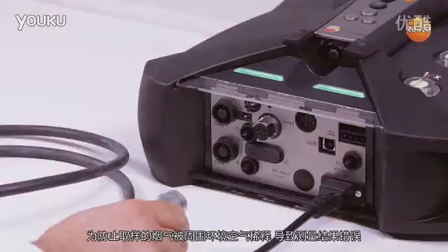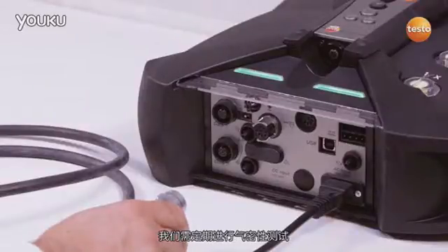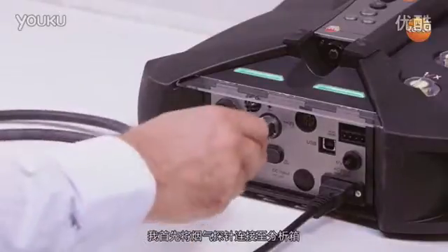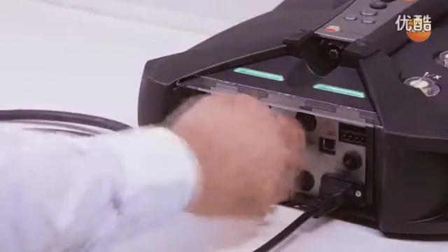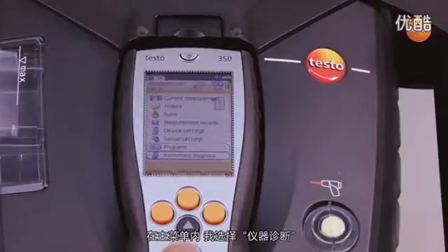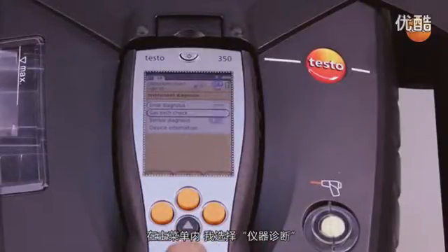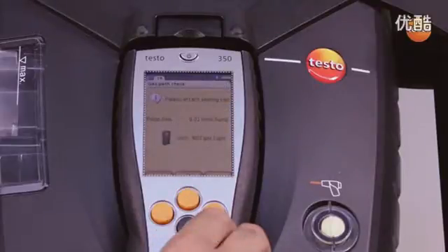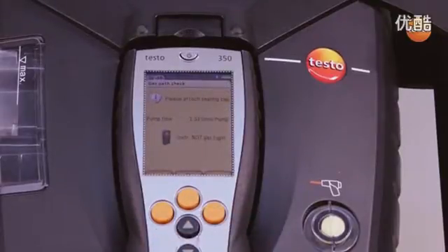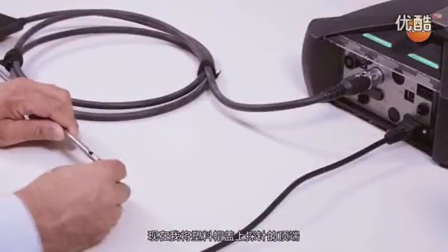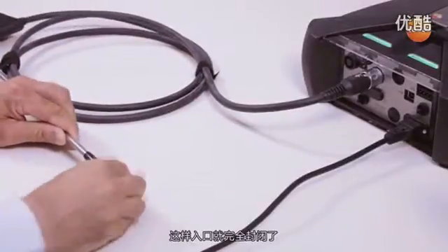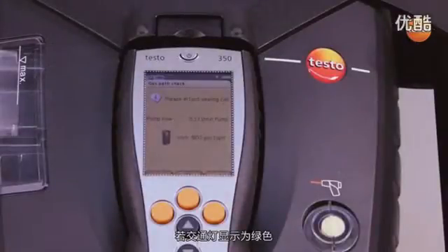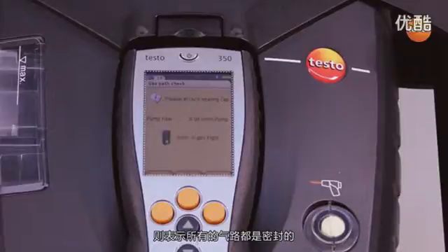The tightness test should be carried out regularly in order to ensure that the sampled flue gas is not diluted by the surrounding air, which would falsify the measurement. Before I begin with the gas path test, I connect the flue gas probe to the analyzer box. In the main menu, I select the sub-menu Instrument Diagnosis and then Gas Path Check. The pump flow is shown in the display. I now place the plastic cap on the flue gas probe tip so that the opening is completely covered. When the traffic light shows green, all gas paths are tight. If the traffic light shows red, the gas paths are not tight and must be tested.